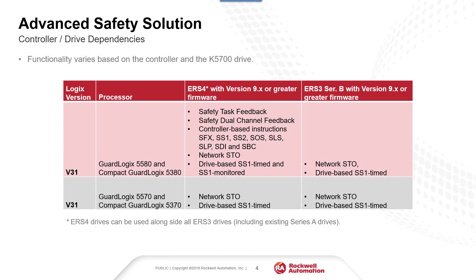Lastly, let's review the features available for an advanced safety motion solution based on the Logix controller and the Kinetix 5700 drive used. When using an L8 GuardLogix controller, the Kinetix 5700 ERS-4 drive provides all the advanced safety functionality. The features include the ability to bring motor feedback into the controller safety task — either single or dual channel depending on the PL or SIL level the system needs to achieve — access to all the controller-based drive safety instructions, network STO, and both drive-based SS1 timed and SS1 monitored safety functions.